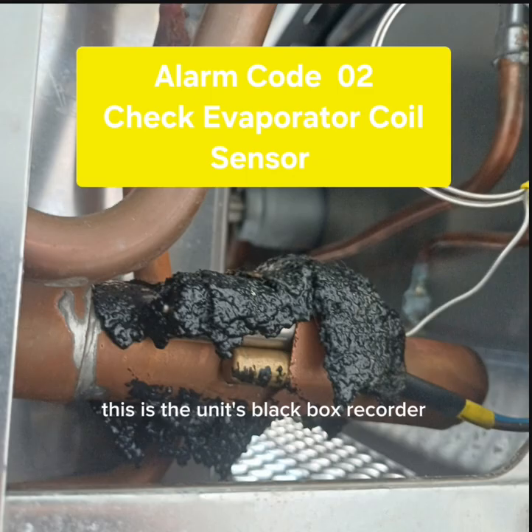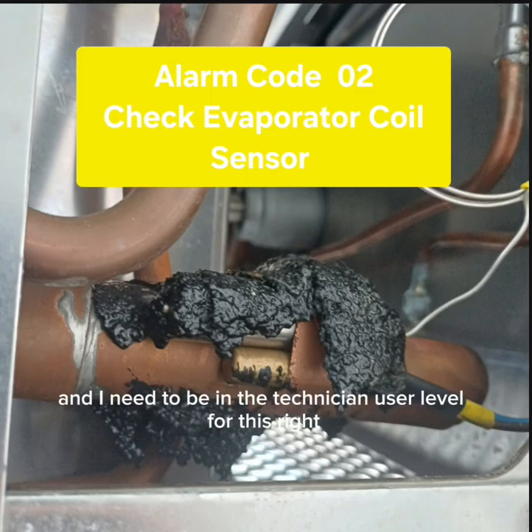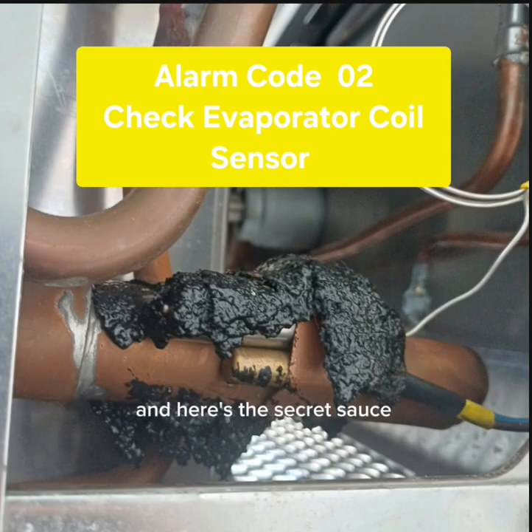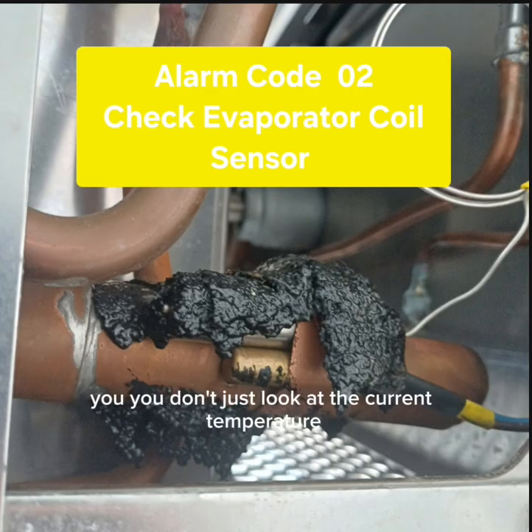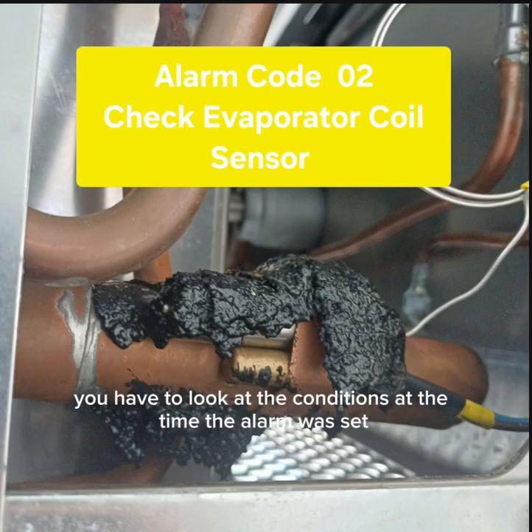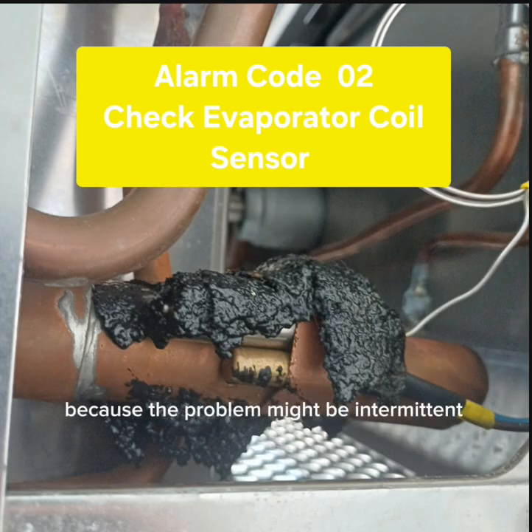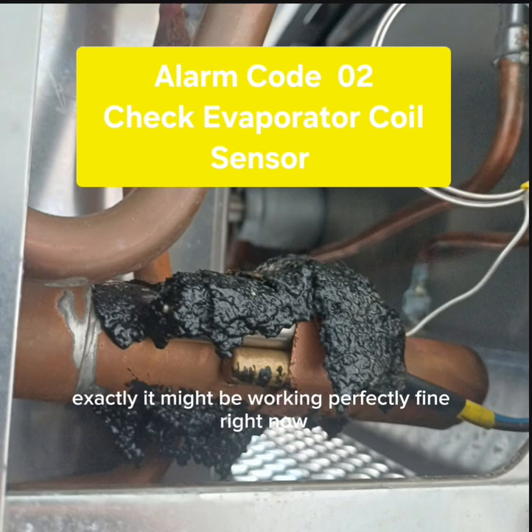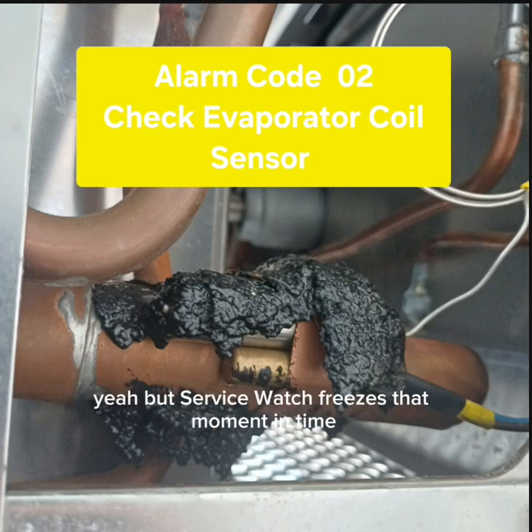This is the unit's black box recorder. It logs all the sensor data every few minutes. And I need to be in the technician user level for this, right? Absolutely. Yeah. And here's the secret sauce. You don't just look at the current temperature. You have to look at the conditions at the time the alarm was set. Because the problem might be intermittent. Exactly. It might be working perfectly fine right now while you're standing there. Yeah. But Service Watch freezes that moment in time.